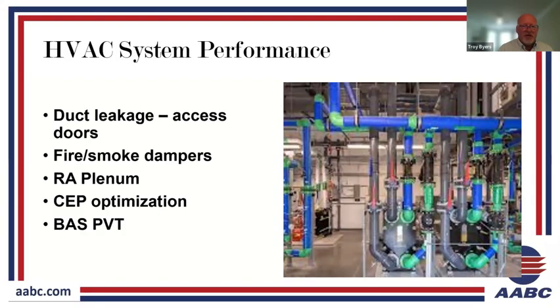When we use the acronym PVT for the BAS, the Building Automation System, PVT is a performance verification test that we see in federal work. It's in the specifications that the controls contractor go through a performance verification test, basically a point-to-point check, to ensure that each controller or controlled device is receiving the proper signal and responding accordingly. For instance, a damper that controls outside airflow, when it's commanded to 0%, that it actually closes, and at 100% fully opens. If there's a flow measuring station associated with that damper, that the damper responds to flow set point changes, proving that the flow station works properly and that the damper responds properly to its set point changes, but applying that to every single controller on the project.